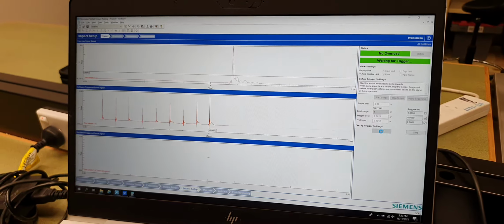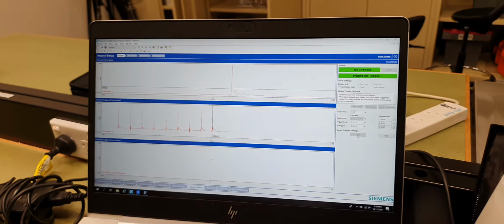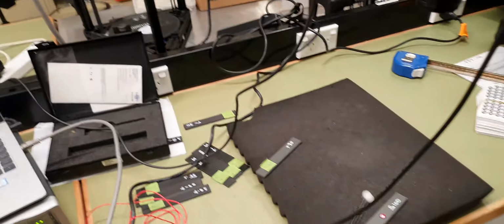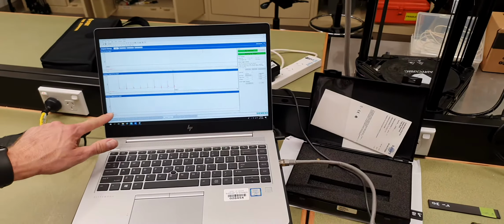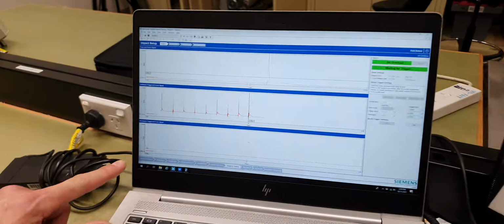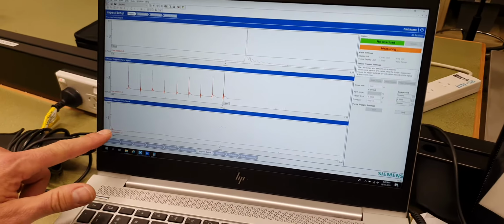Verify the trigger settings. I press the start button down here, and then I'm looking at this hardware triggered force signal down here underneath. So I go back to my sample and tap it, and if it's properly triggered, it's going to capture that impulse, and that impulse should be at the start of the waveform, which is over here to the left hand side.